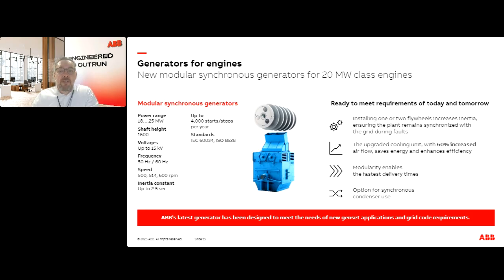The main features: we can install one or two flywheels to increase the inertia, which ensures the plant remains synchronized with the grid during faults. We've also made a completely new cooling design for this machine, with roughly 60% increased airflow within the generator, which saves energy, enhances efficiency, and makes the footprint smaller than traditional ones. Modularity means different applications, but also, because of modular designs like these flywheels and cooling units, it means faster delivery times. As the latest innovation, this generator is suitable for synchronous condenser use, which I'll explain in more detail in the coming slides.